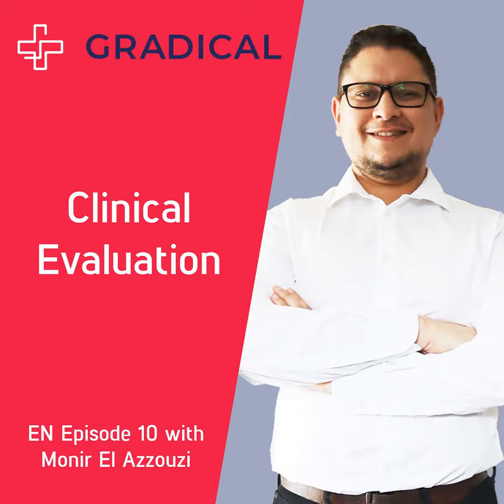If you have, for example, executed a clinical investigation, then this is something that you can use to explain that I have tested my device on humans and here is the result. If you have not done some clinical evaluation, you can maybe use some equivalent devices to say, here is the device that I will be using as an equivalent. And the objective of using an equivalent device is not to say, oh, my device is equivalent to this device that is already on the market, and so we are fine, my device is safe.